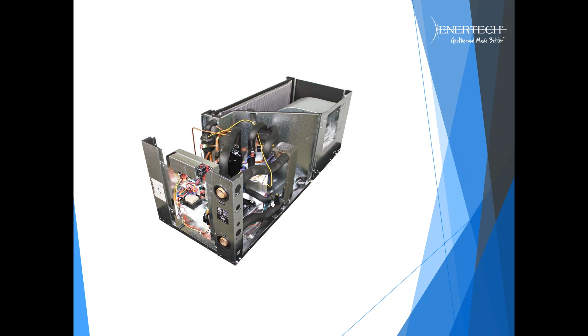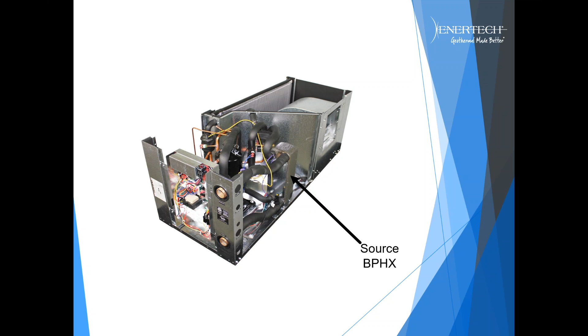So to take a closer look at the product, here's an exploded view of inside the ZSCT. First thing I want to mention again is the source brazed plate heat exchanger. You can see right there. And this one shows an extended range application, so there's a spray foam application on the brazed plate. But notice how small and compact the brazed plate is versus a coaxial heat exchanger. That took out about 70 pounds of weight and also made the product more efficient.